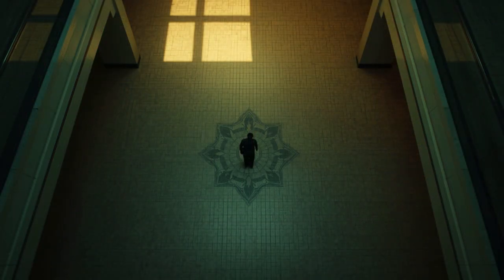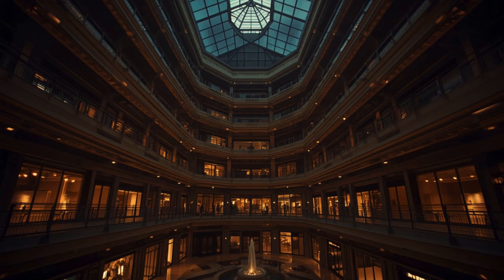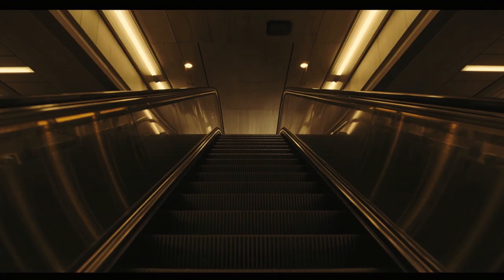Then consider the openness. The atrium, which gave the mall its sense of grandeur and its quality of connected, multi-level space, was from a fire safety perspective a significant liability. In a conventional multi-story building, each floor is separated from the floors above and below by fire-rated floor assemblies, horizontal barriers of sufficient thermal resistance and structural integrity to slow the spread of fire and smoke from one level to the next.